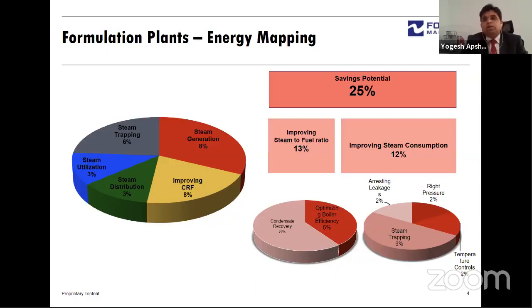The second aspect is improving the steam consumption inside the process, which is outside the boiler house. This consists of steam trapping, which is 6%, and then smaller aspects like pressure drop, temperature controls, and leaking. All in all, we envisage a 25% potential in any of the formulation plants, which we take care of during the design stage, or which we can do if the plant is existing.